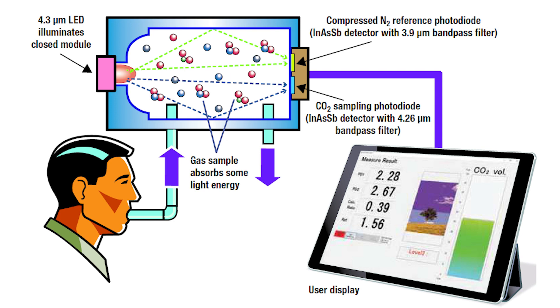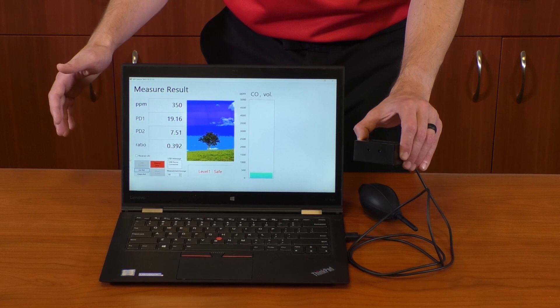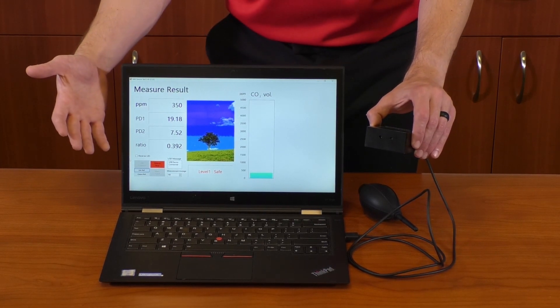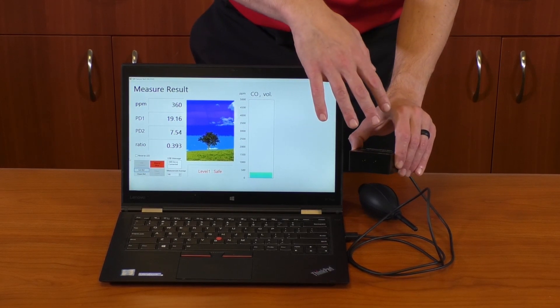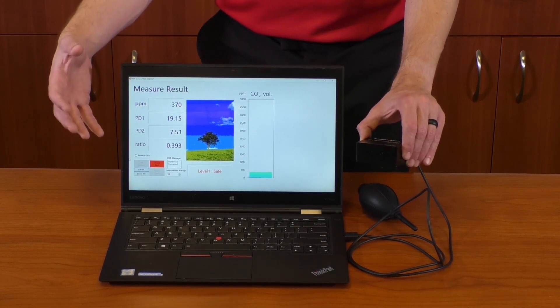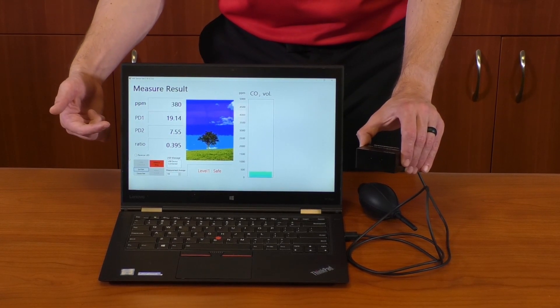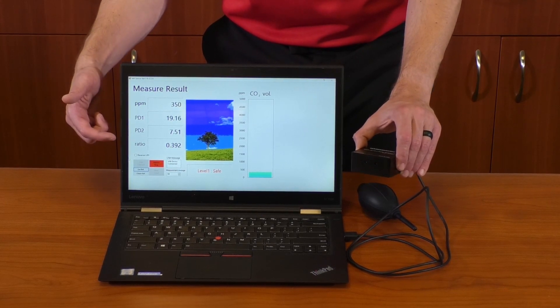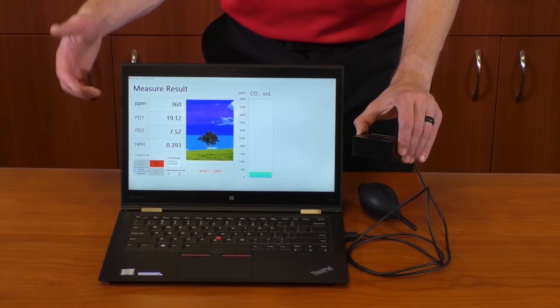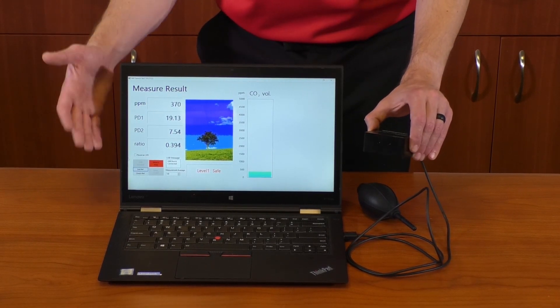Now one diode, especially the one at 4.3, is going to see a whole lot more signal initially — that's where the LED is emitting. Now, on the principles of absorption and Beer's Law, if carbon dioxide enters this non-dispersive infrared space, some of that light is going to get absorbed or gobbled up, and that measurement channel is going to see a lower signal. All this comes down to the ratio of those signals, which directly relates to parts per million — that's what everybody wants: the concentration in real time.